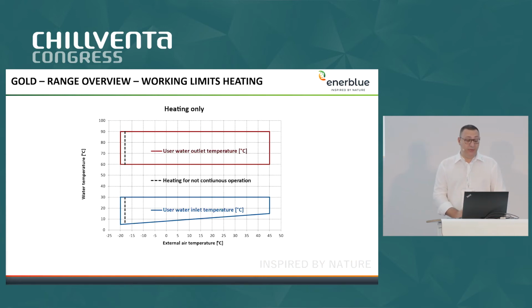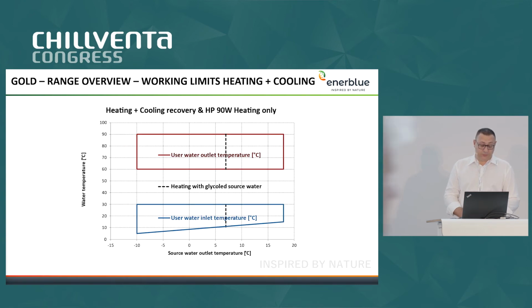In terms of working limits for heating application, you can see we have external air temperature on the lower part of the chart and water temperature on the left part. So you can easily see we can work from minus 20 ambient temperature up to 45. And in all these conditions, we can produce water up to 90 degrees. So the unit is perfectly able to satisfy all the requirements for the domestic hot water production or industrial heating production.